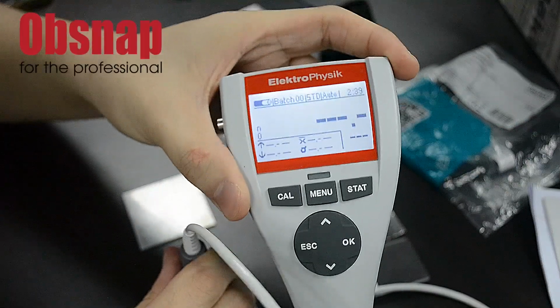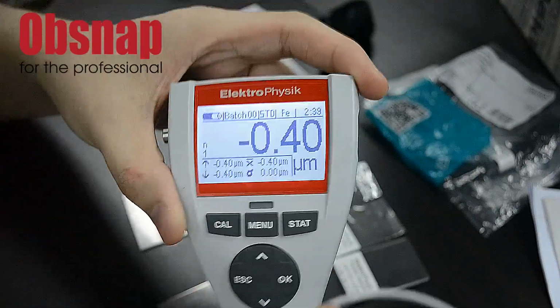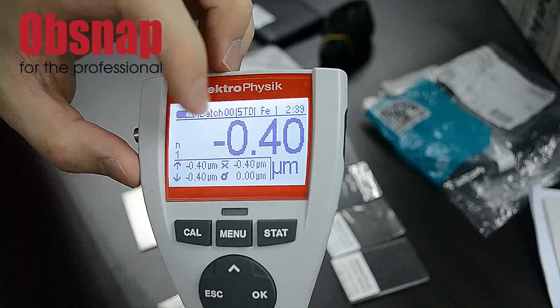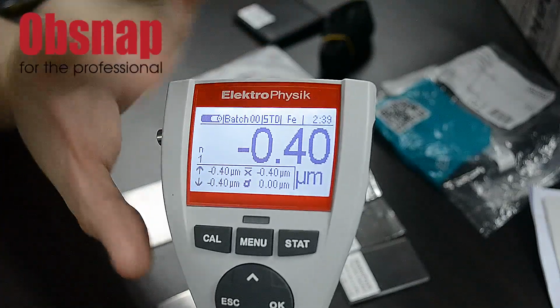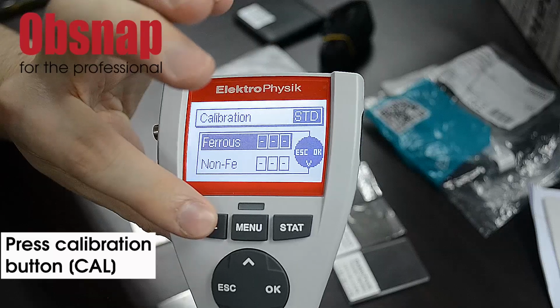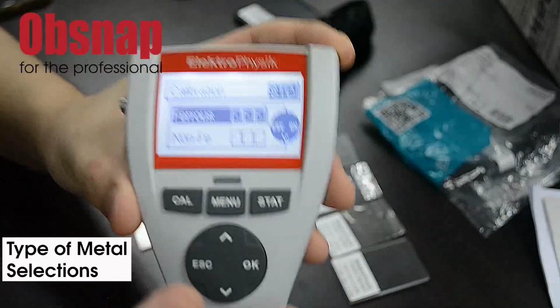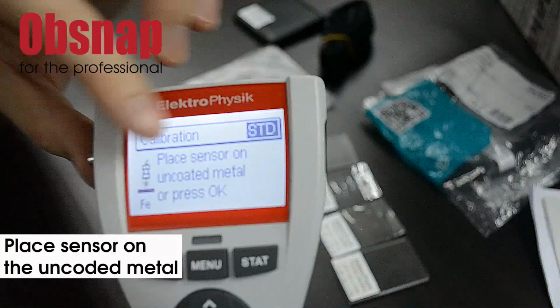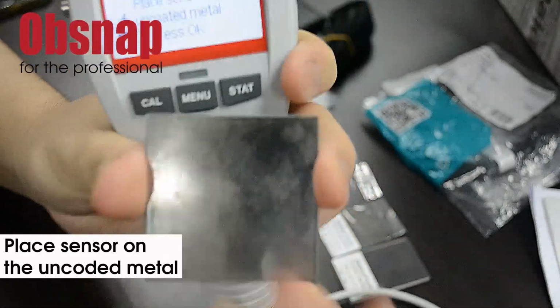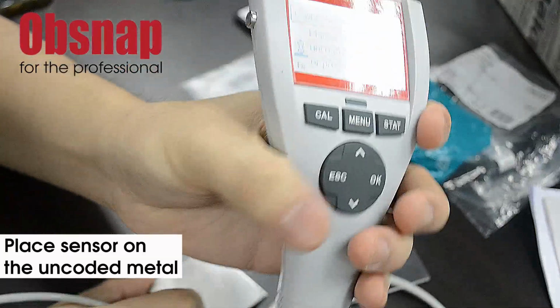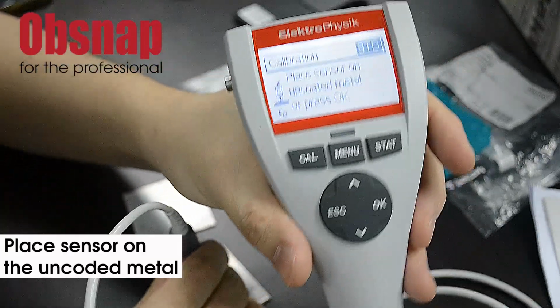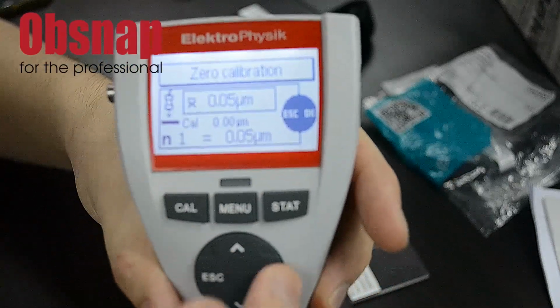Alright, so we just place it on the metal. You can see we are getting 0.4 micron. So it's not accurate because we haven't done any calibration. So let's just do calibration. We press the calibration button. It allows us to choose between ferrous and non-ferrous. So let's do the ferrous material first. So press OK. It will ask us to place the sensor on the uncoated metal and press OK. The uncoated metal means the zero plate given by ElektroPhysik. So we just place the probe onto the metal. And you will get a very small reading here. So just press OK again.